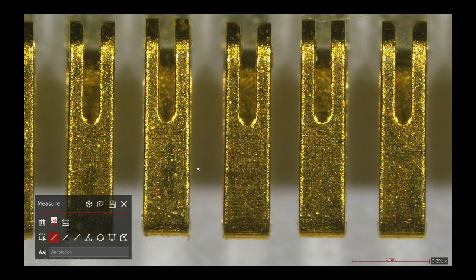Furthermore, you have the option of line creation. That's a simple line. You can create arrows, and then you can, of course, use the selected item and make it disappear. Then you have here the line measurement option. And when you right-click on your mouse, when you have activated the line measurement or any of the other measurements that I'm going to show you, you get actually a digital magnifying glass that shows you how good or how bad you are in positioning. So here I put the next position on the other side, and then you see here that my measurement line is not straight. But of course I can correct that and straighten it up, and then I get automatically the distance.